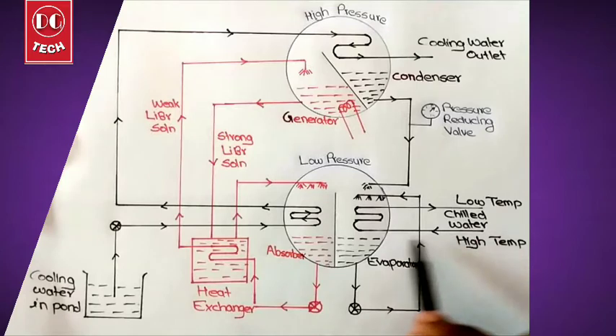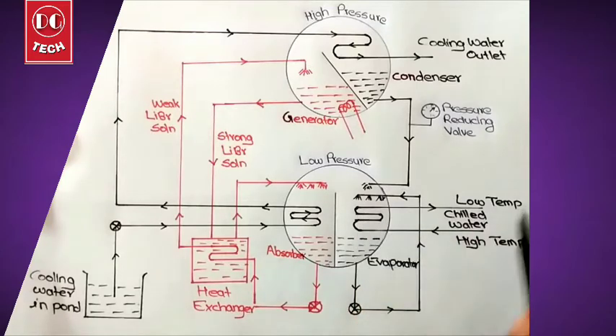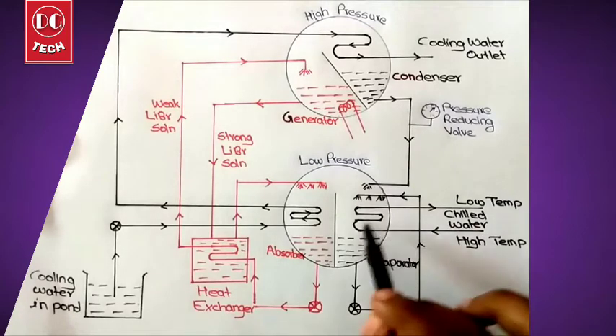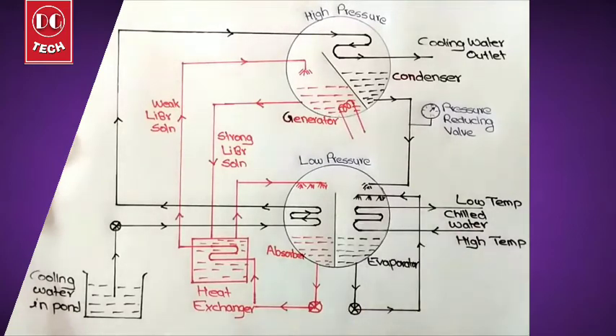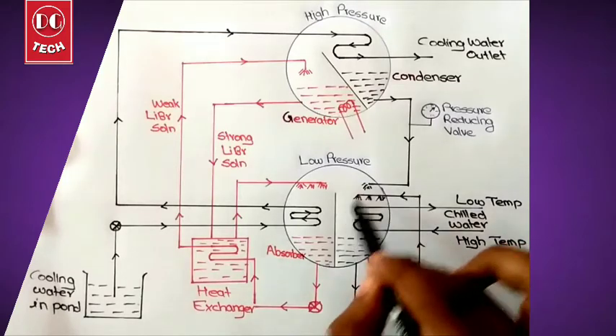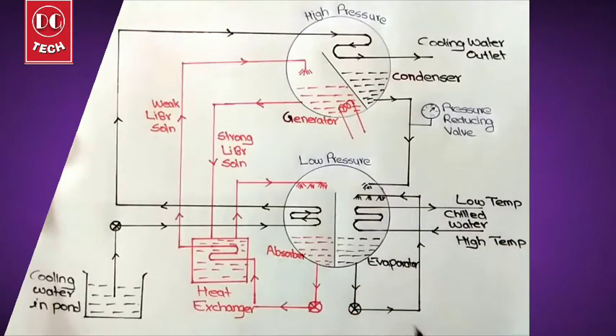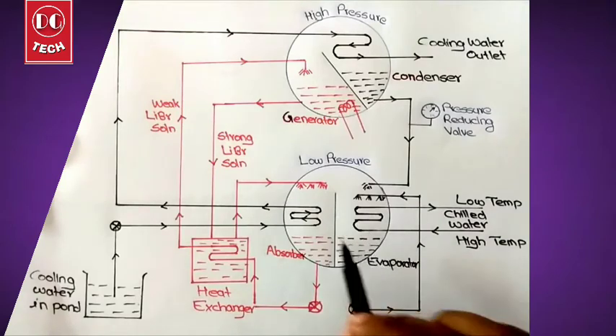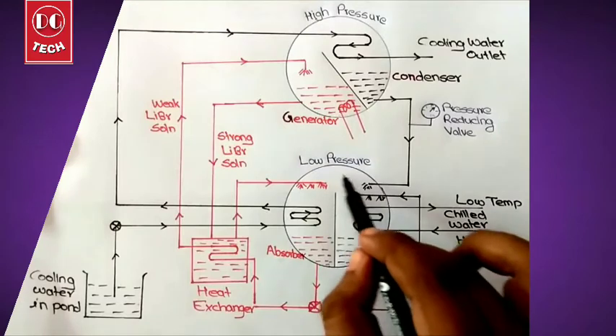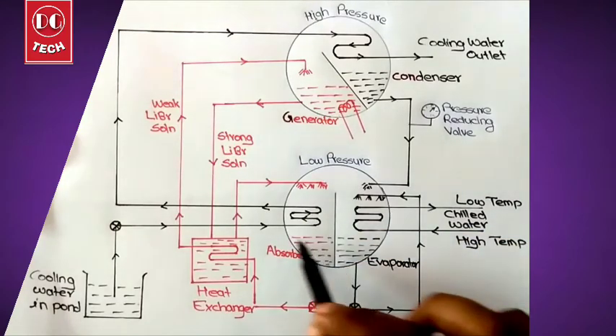We need to get chilled water which is flowing through this pipe. In the evaporator, it is filled with water and using a pump, the water is pumped and sprinkled into the evaporator. Since the pressure of this chamber is less, the water will get evaporated and move towards the absorber.